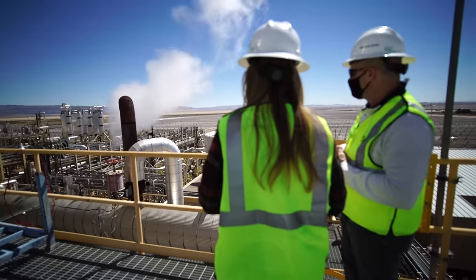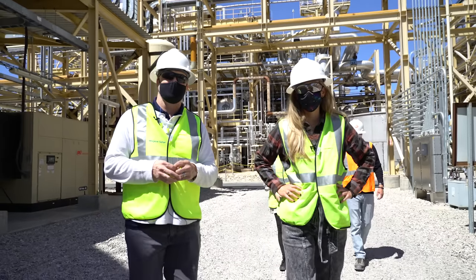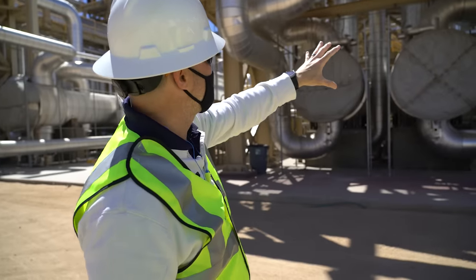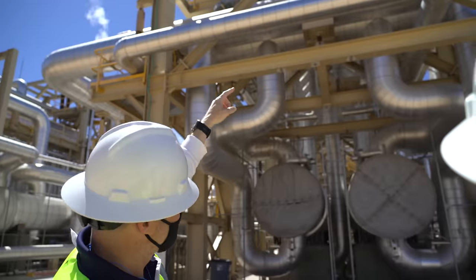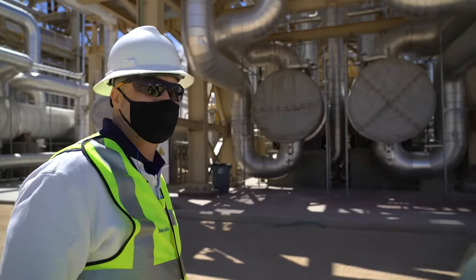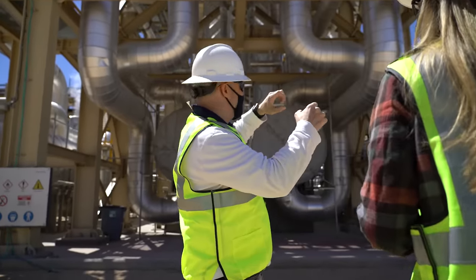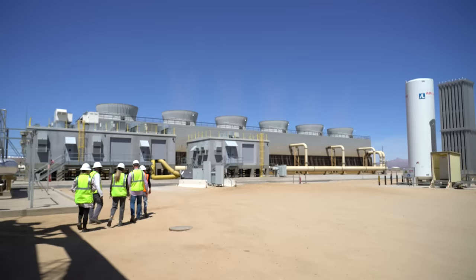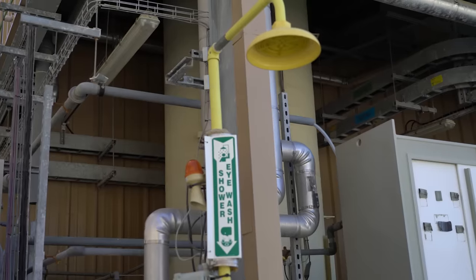Going backwards from the turbine: where the steam is created is where the hot material comes in and creates steam. These are the steam generators. It's actually a natural circulation system — the bottom part is where you're boiling the water, the water goes up, and a steam drum on top drips back down, creating a natural circulation loop. The heat transfer fluid comes in through thousands of tubes in a U-shape and goes back out. It creates what's called saturated steam, where gas and liquid water coexist at the same temperature due to high pressure, then expand to push the turbine.